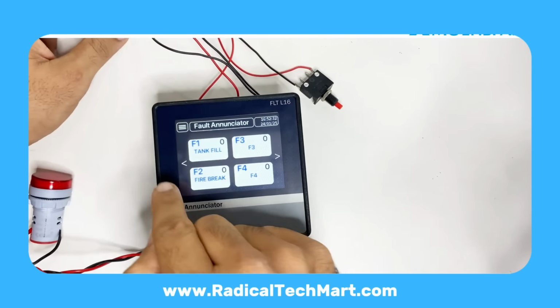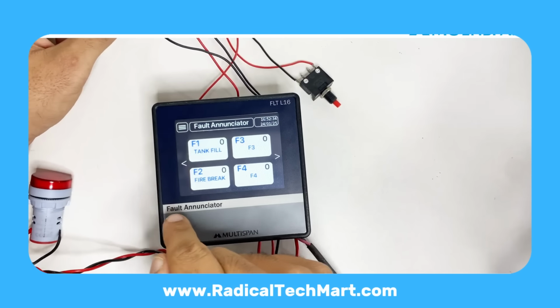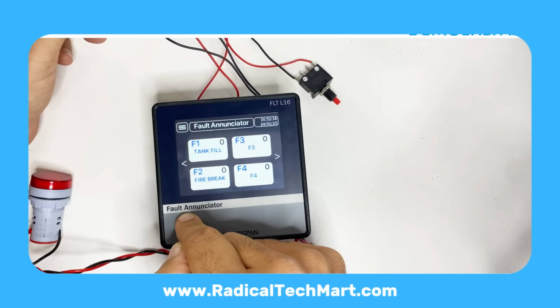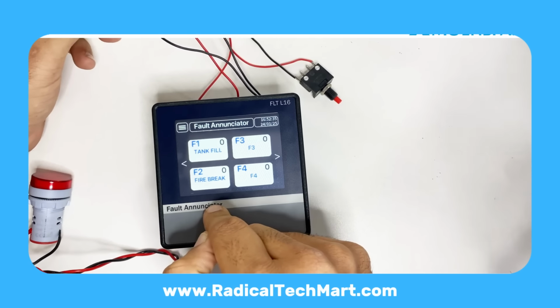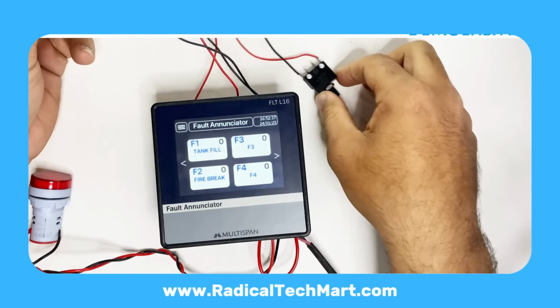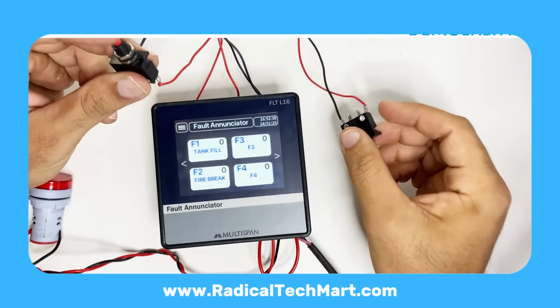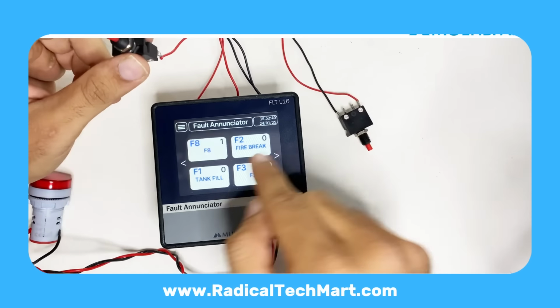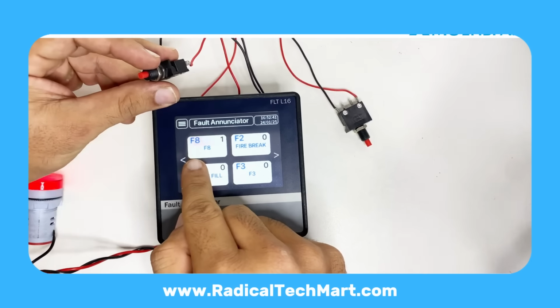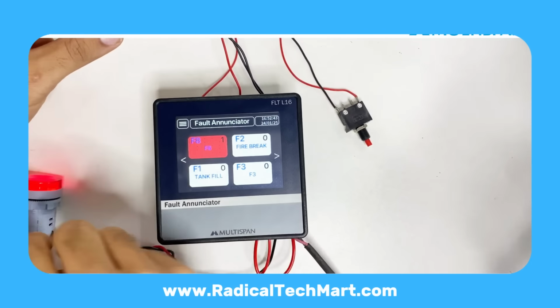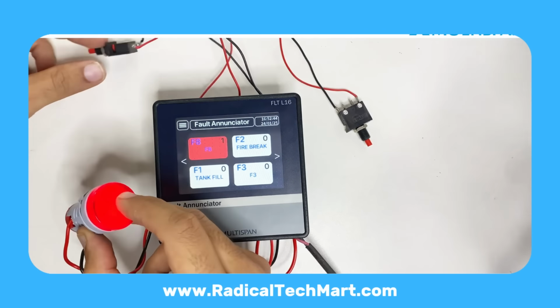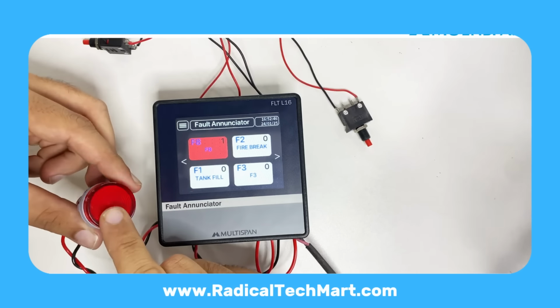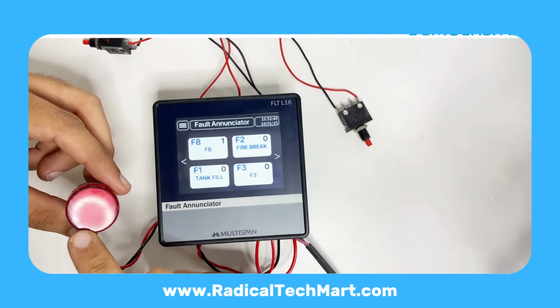Now let's see how faults are indicated on the screen. For example, we have set F1 equal to tank fill. F2 equal to fire break. When a fault occurs, the corresponding window, say F1 or F2, will turn red. It will also blink, indicating an active fault in the field. The alarm relay will operate as per configuration.